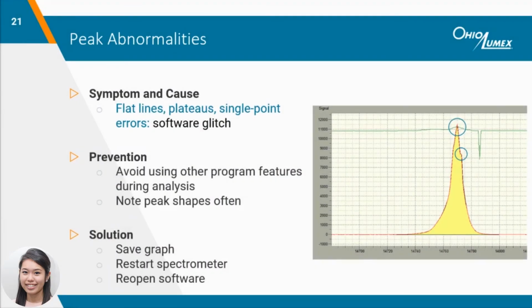Software glitches can sometimes occur on rare occasions. The resulting peaks typically contain flat lines such as plateaus and single point errors, as seen on this peak here. To avoid glitches, it's recommended to avoid using program features, like switching back into calibration mode or loading the measurement database during analysis. It's good laboratory practice to view the entire peak to ensure the most accuracy. If you do spot a glitch, discontinue analysis right away, save the graph, restart the spectrometer, and reopen the software.